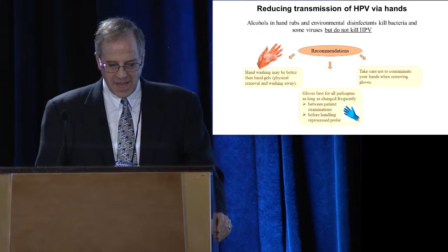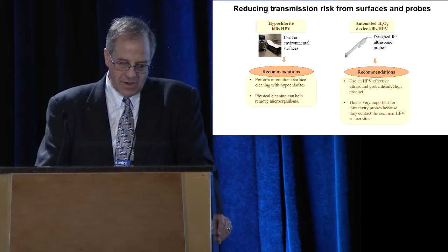Reducing transmission risk from surfaces and probes. Hypochlorite kills HPV, so you might want to consider intermittent surface cleaning with hypochlorite, or physical cleaning can help remove the microorganisms. Automated H2O2 devices kill HPV, and these are designed for ultrasound probes. This is the only thing I know so far, besides bleach and this high concentration peracetic acid, which you can't get, that will kill HPV. And this is very important for intracavity probes because they contact the common HPV infection sites.